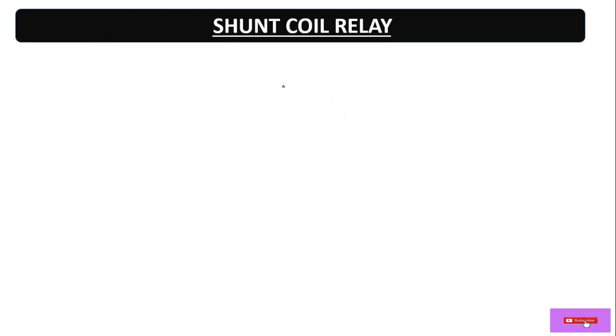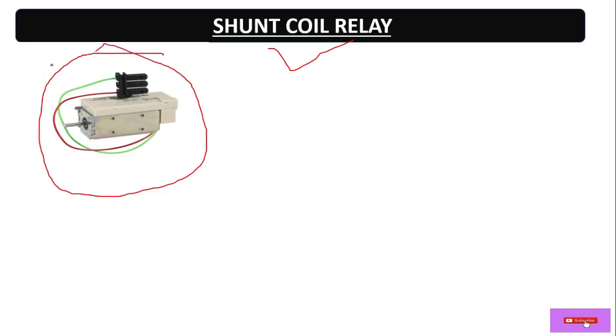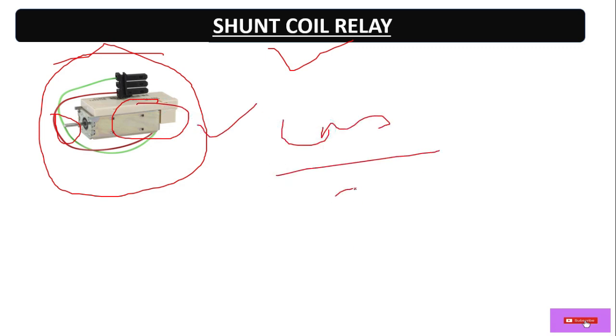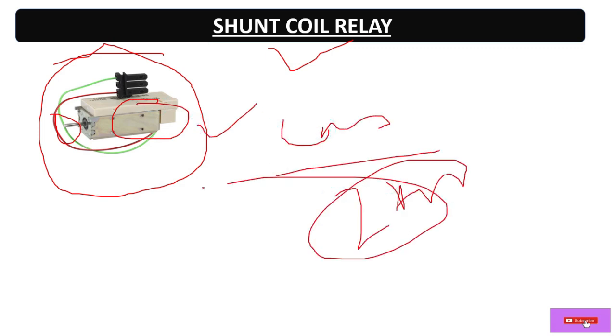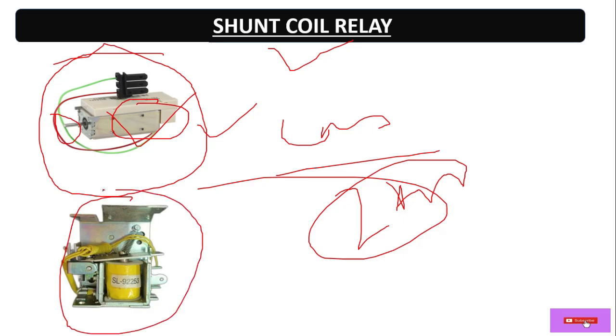Now let's discuss each part one by one. First, the shunt coil relay. The function of the shunt coil release — it looks like this: inside it we have a plunger, and inside that is a coil which may be 24V DC operated. This is the shunt coil.